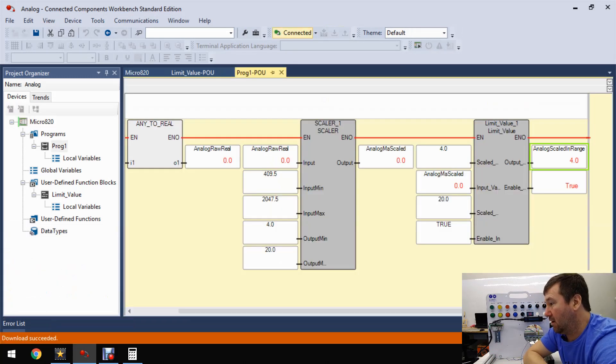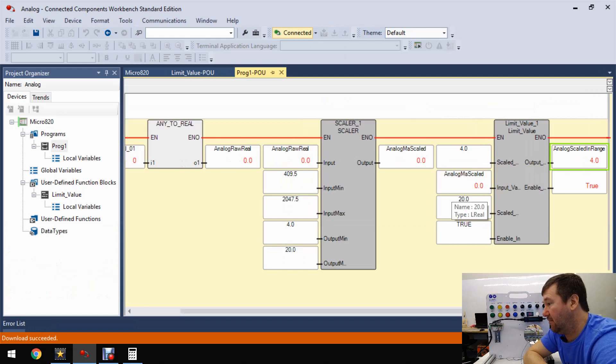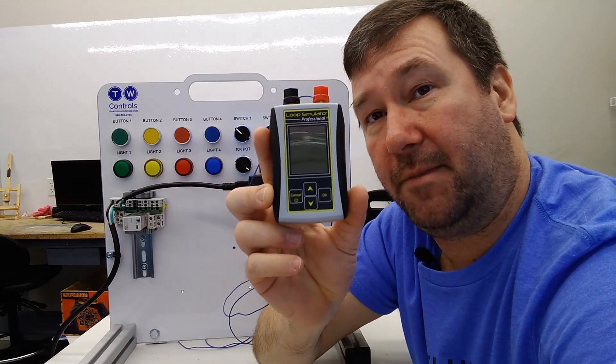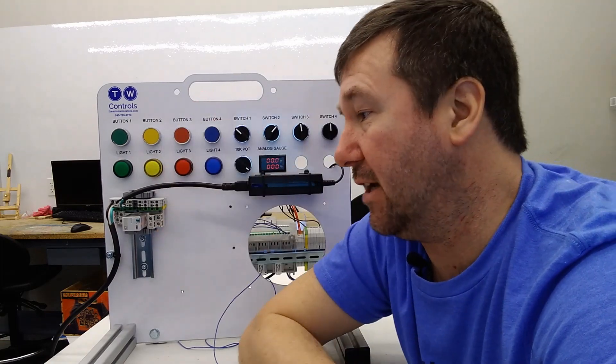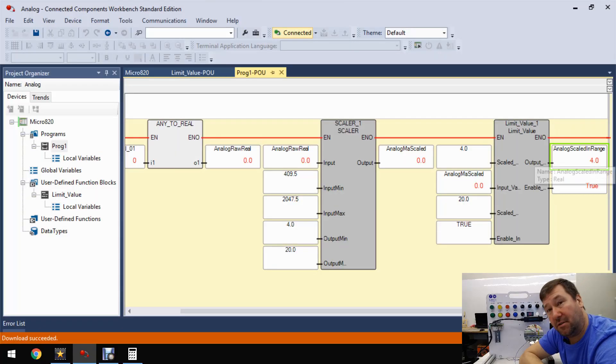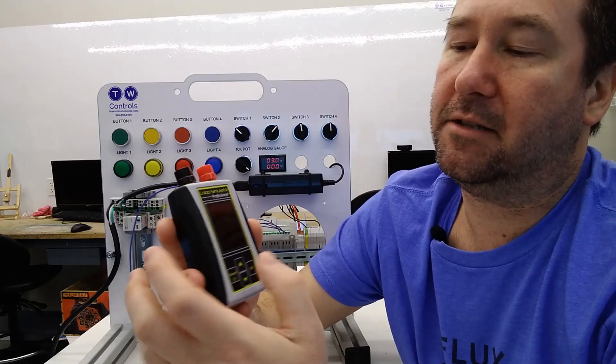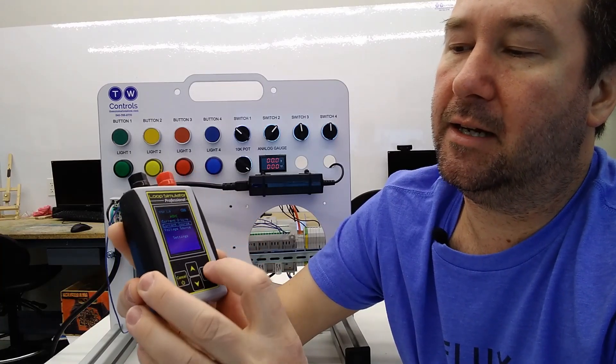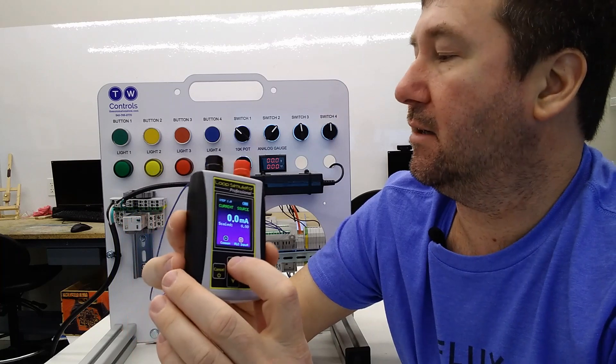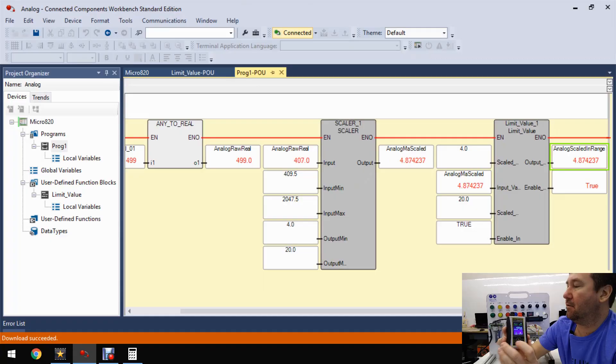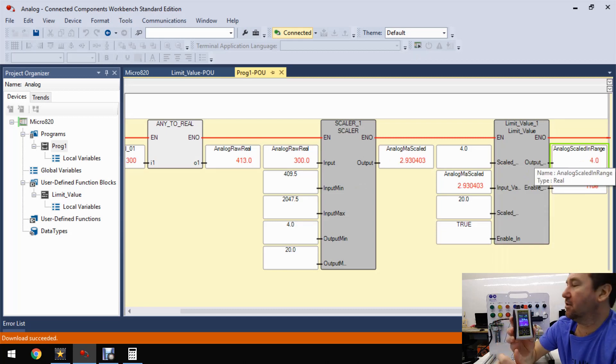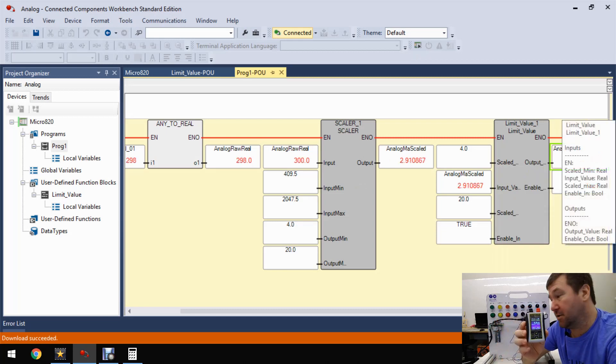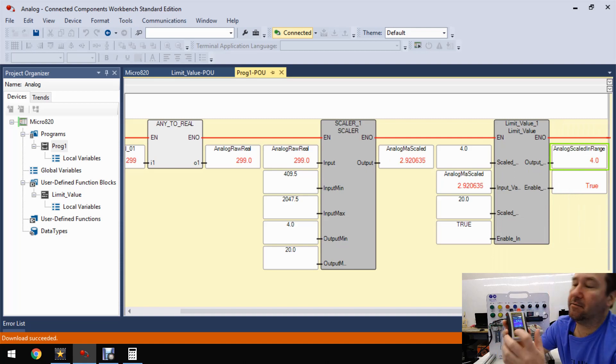All right, let's go over to our new limit instruction. See what it's doing. Our scaled milliamp value is zero because in the time that we've been adding this, our milliamp simulator is going into power save mode. But our scaled input within range is four, which is exactly what we wanted. So now let's power up our simulator and let's start bringing its value up. So now we're at four milliamp and we're showing four milliamp. We go down to three though, we're showing four on our scaled value.